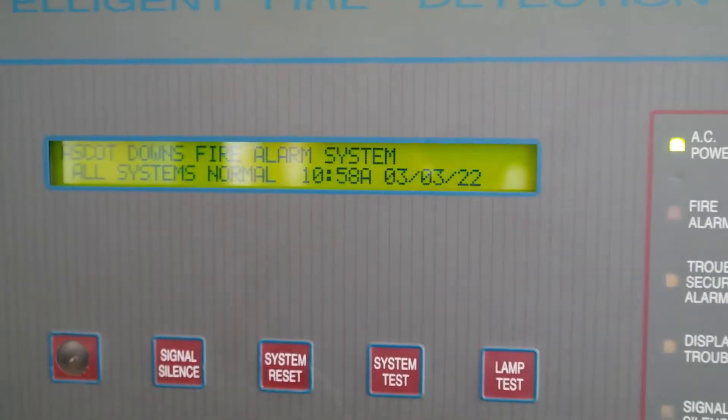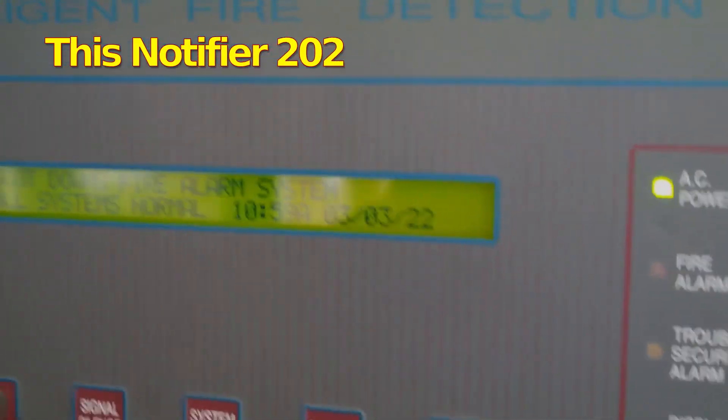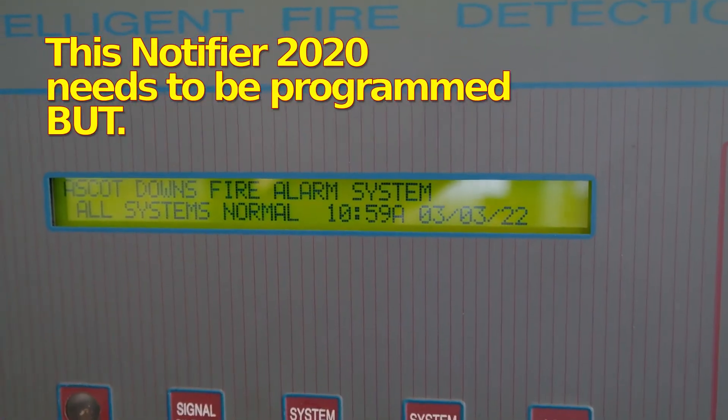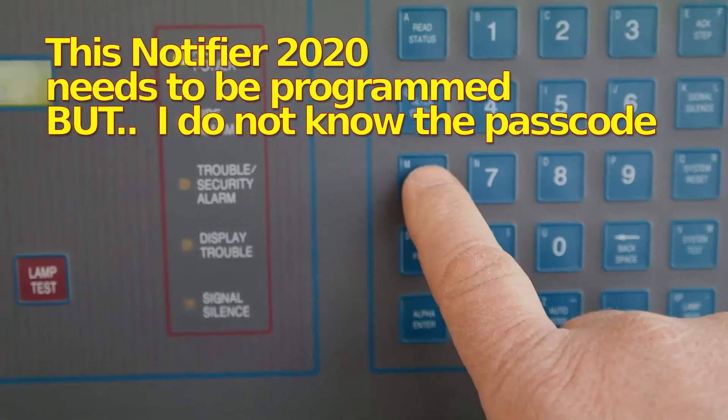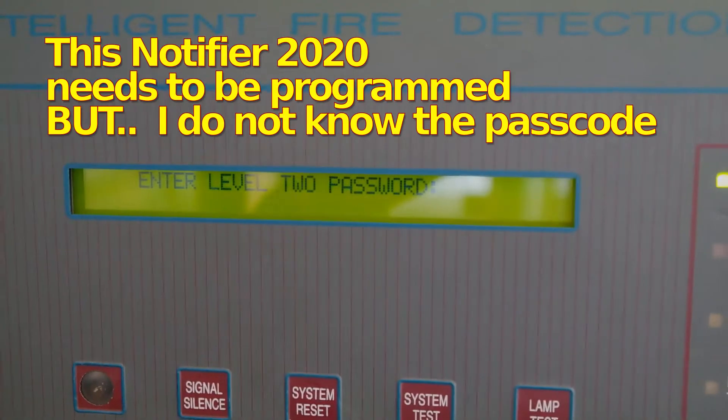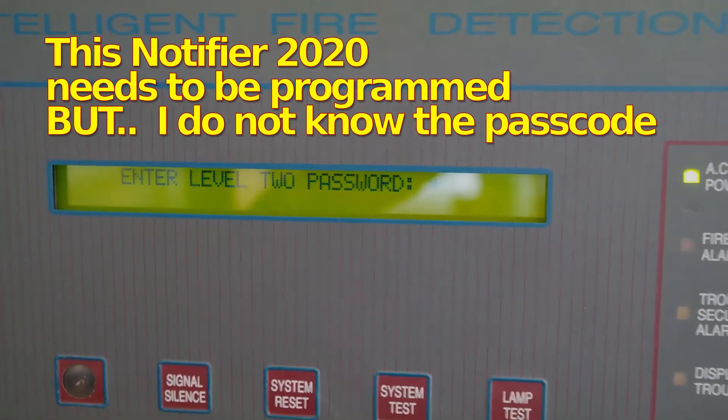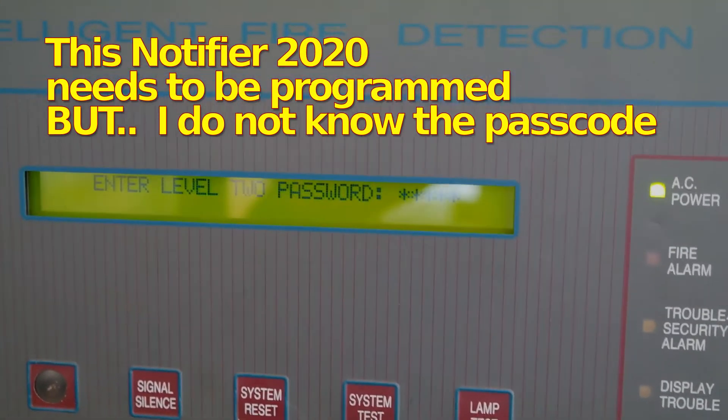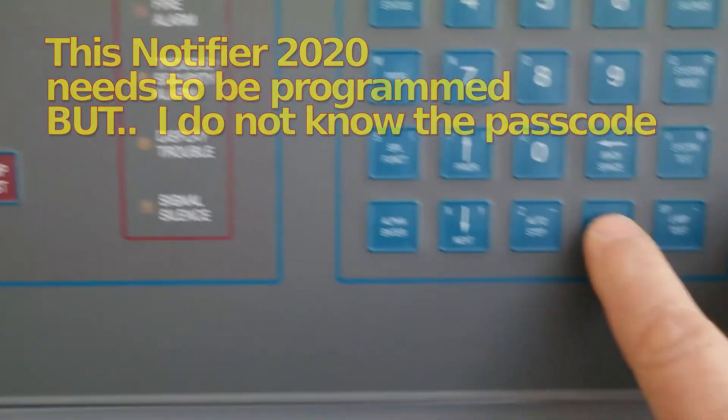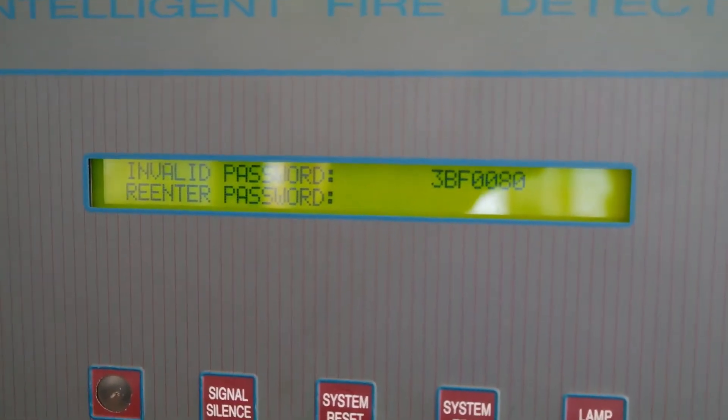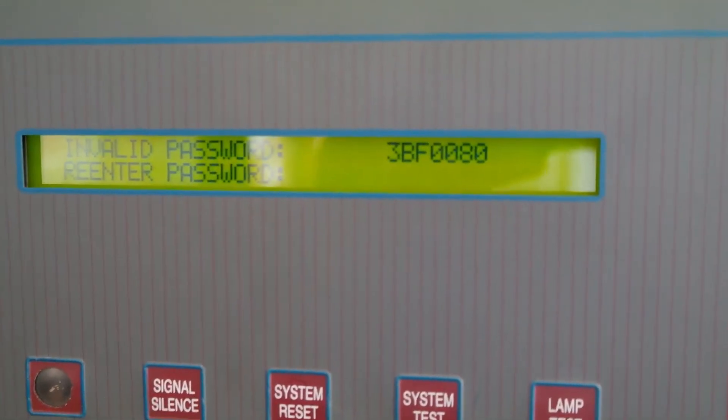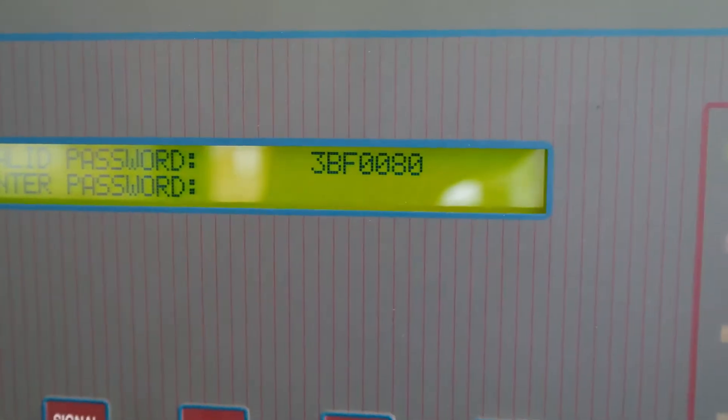Today we're going to work on a 2020 Notifier panel and find out that it requires a passcode to do any programming. When we press program, it asks you to enter the programming password, which factory default would be 00000. When you press enter it rejects it, but it gives you that error code right there. Now we're going to plug that error code into the computer and figure out the passcode.